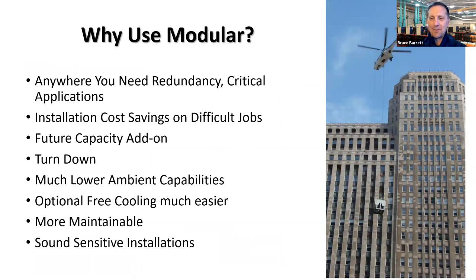It's often said that air cooled is not as attractive or as exciting. And I certainly get excited talking about modular air-cooled chillers because of all the benefits over and above some of our package chiller offerings. Because of the complexity of the job, redundancy and critical cooling requirements are a big part of today's world, both for comfort cooling and critical cooling, being data centers and process applications. They can have a lot of challenges that add a lot of cost, and modular fills a lot of those gaps to reduce that first cost. Installation cost savings as well for the application of modular chillers.